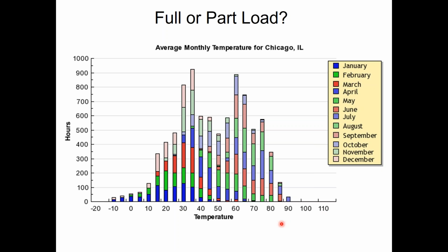I'm going to real quick look at the load diversity for Chicago, and if you guys are up in Wisconsin, which some of you are, I apologize that I didn't put up a Milwaukee slide. I just went with the average number of people that are on here today. In any case, this is my loading profile for weather days for the Chicagoland area. You can see that we have some hours where we're up at 90 degrees, but not a lot of hours. And we have nothing really above 95 and higher. Now, does it ever get above 95? Sure, it does. But statistically, on a 30-year rolling average, it's a very small amount. So that line is so little on here, you can't even really see it.